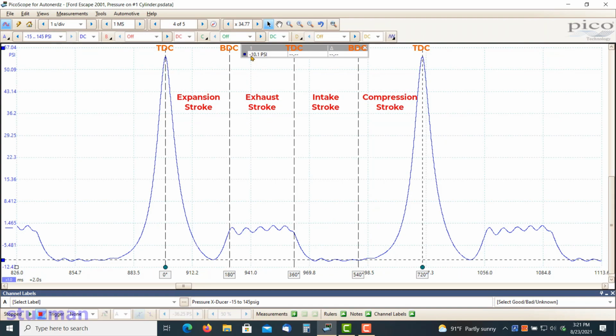Now that pressure is minus 10.1, and if we wanted to know what that is in inches of mercury, we can pull up our calculator and say 10.1 times. For every psi of pressure, that's equal to approximately 2.036 inches of mercury. So if I type in 2.036, that's going to be about 20.5 inches of mercury.